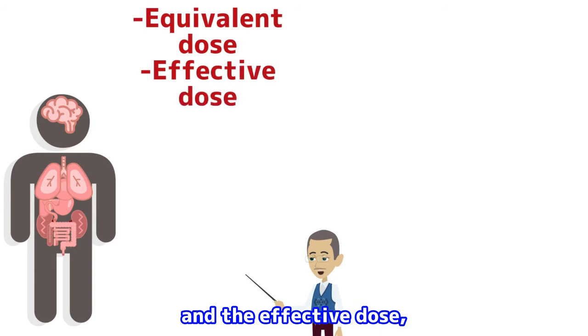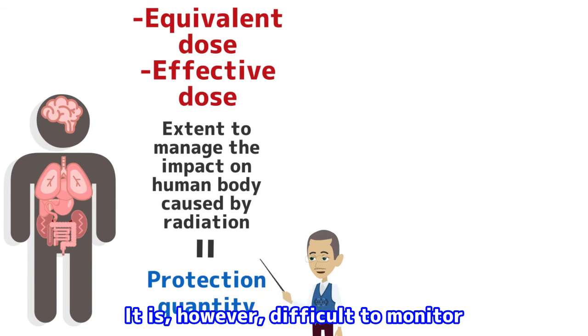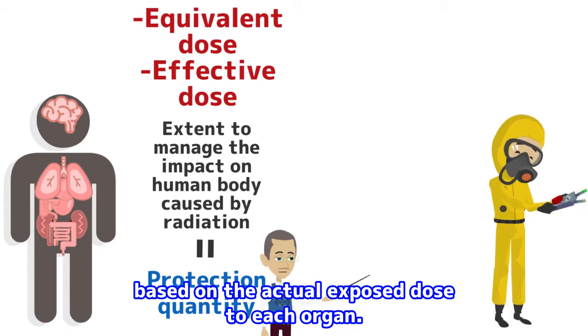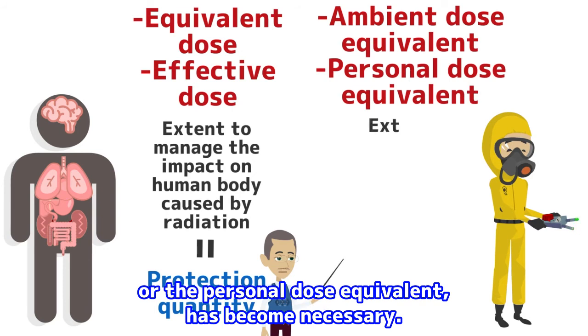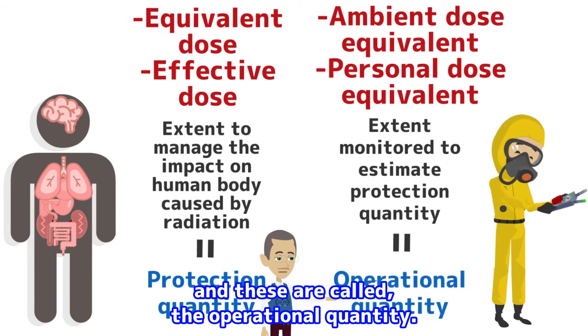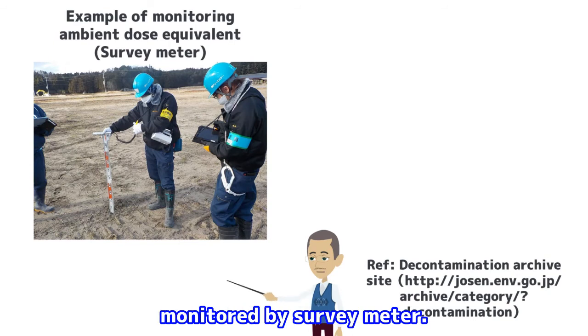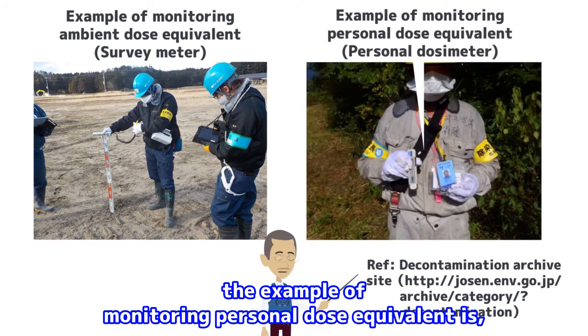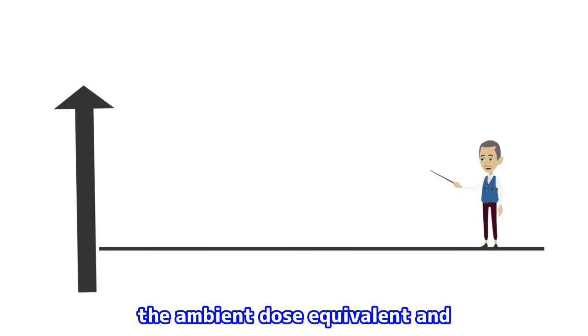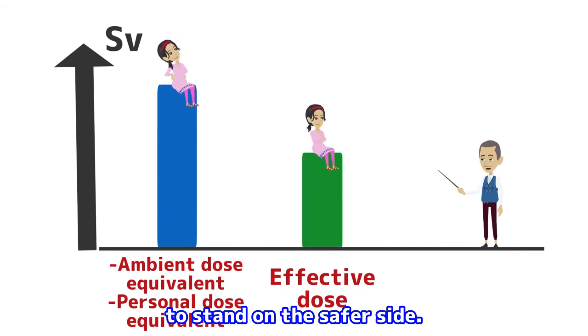That's right. The equivalent dose and the effective dose are the extent to manage the impact on human body, and these are called protection quantity. It is, however, difficult to monitor these protection quantities, because they are calculated based on the actual exposed dose to each organ. Therefore, the ambient dose equivalent or the personal dose equivalent has become necessary. These are the measurable quantities to estimate the protection quantity, and these are called the operational quantity. Specifically, the example of monitoring ambient dose equivalent is the air dose rate monitored by survey meter. In addition, the example of monitoring personal dose equivalent is the personal exposed dose monitored by personal dosimeter. Moreover, importantly, the ambient dose equivalent and personal dose equivalent are always larger than the effective dose, in order to evaluate conservatively — in other words, to stand on the safer side.